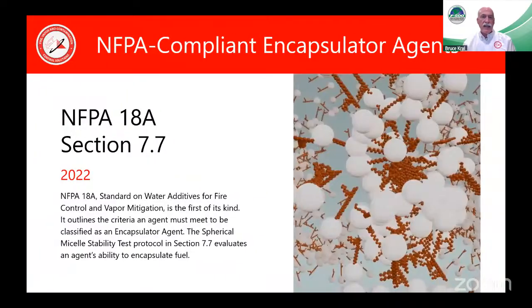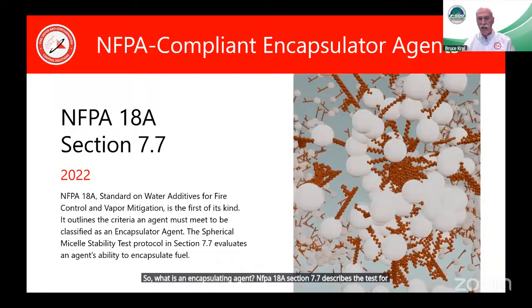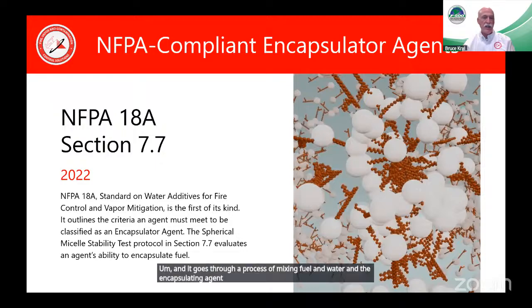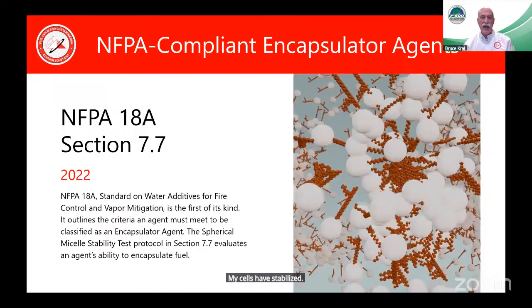So what is an encapsulating agent? NFPA 18A section 7.7 describes the test for determining whether or not an agent is an encapsulator agent. It goes through a process of mixing fuel, water, and the encapsulating agent, making sure that it cannot be relit, then sitting for 2 hours to confirm the micelles have stabilized and will not reignite.